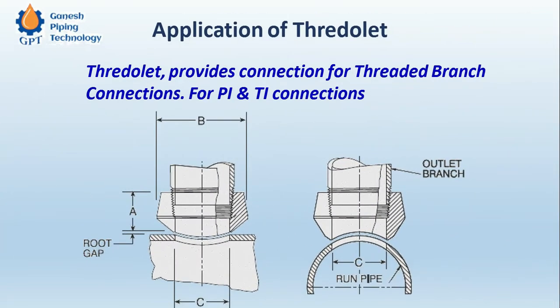ThreadOlet provides connection for threaded branches like pressure indicators and temperature indicators. The header side of the ThreadOlet is butt welded — full penetration butt welding is done on that side — and on the branch side we have an external male threading. The internal threading is provided by the ThreadOlet.